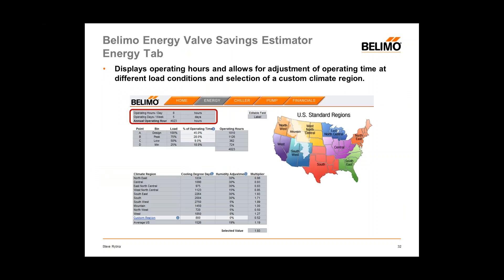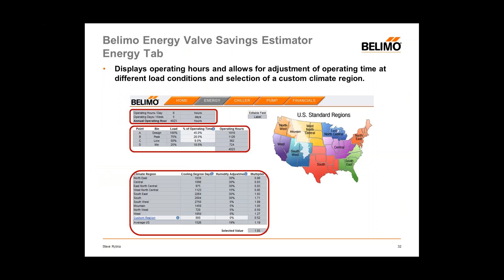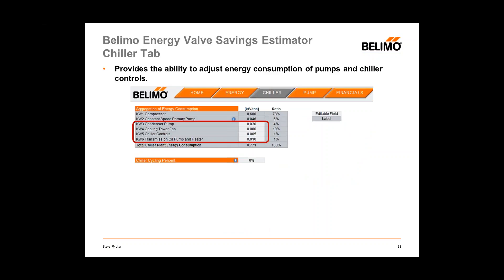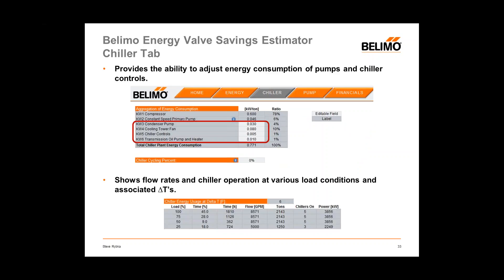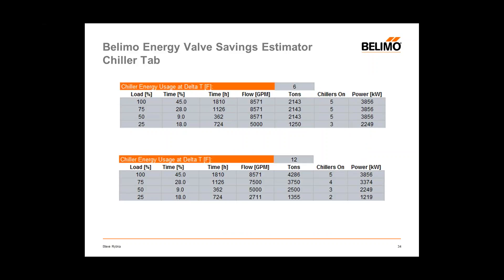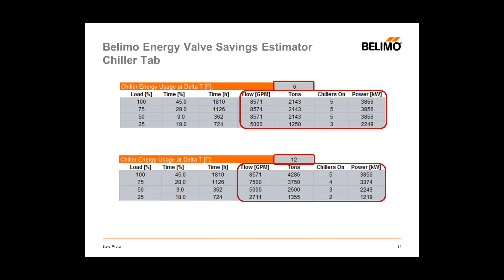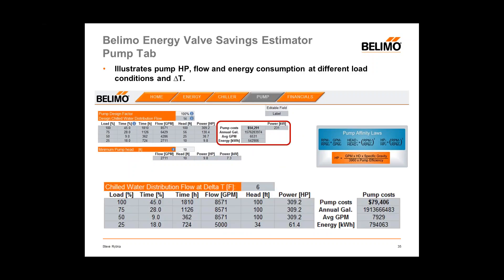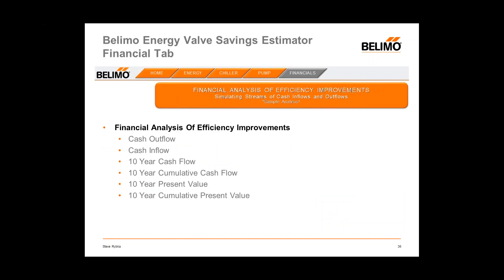The home sheet also provides a financial analysis and a greenhouse gas reduction figure based on decreased energy consumption. The energy tab allows you to adjust operating hours at different load conditions and create a custom climate zone if needed. The chiller tab allows you to adjust the ratio of energy consumption for pumps, fans, and chiller controls, and shows different flow rates and plant energy consumption at different load conditions and delta T's. The pump tab illustrates pump horsepower, flow, and energy consumption at different load conditions and delta T's. Finally, the financial analysis tab provides financial information based on energy efficiency improvements made at the central energy plant by improving the delta T.